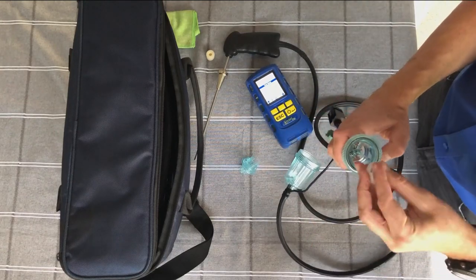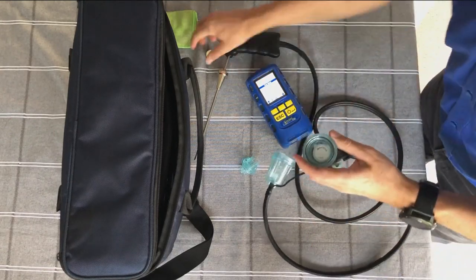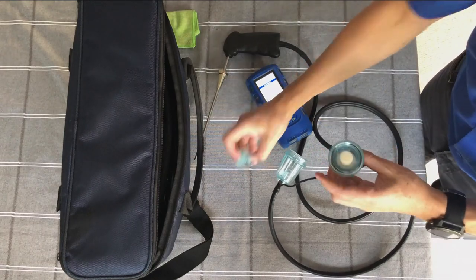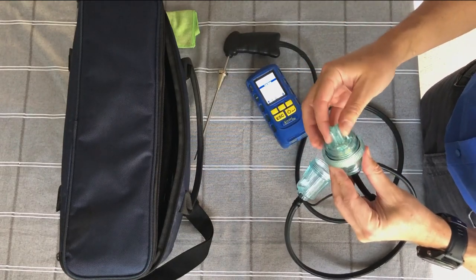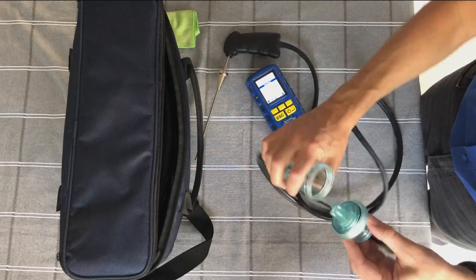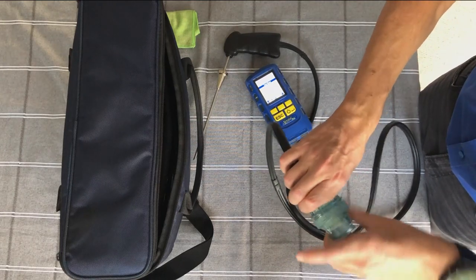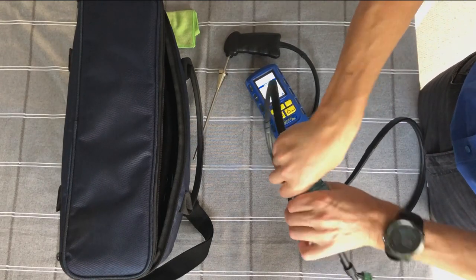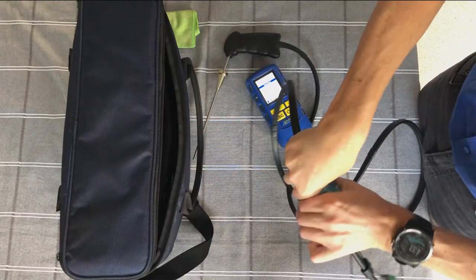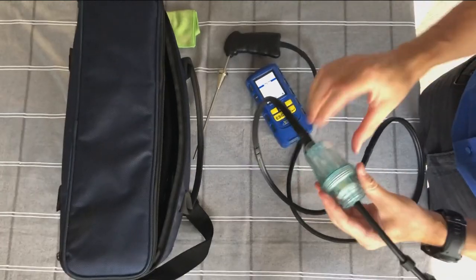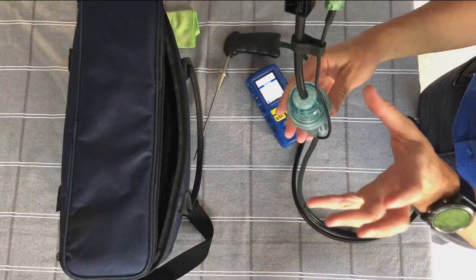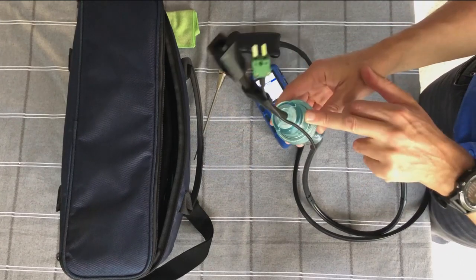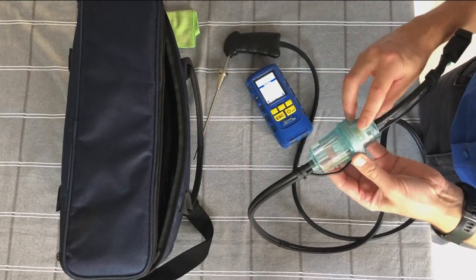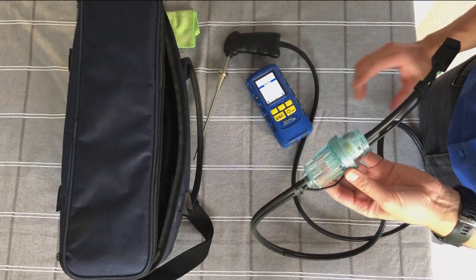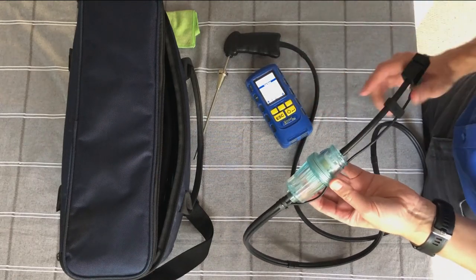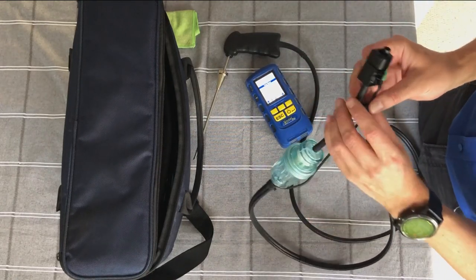Putting all that back together, once you've dried it all out, just push that in there, the filter sits on top, and then if you can see, that carrier sits in the middle and it all goes back together and that bayonet screws tight again all the way down, so you've got a nice airtight water trap. So the filtration is really, really good on Pro, and it's something we're really proud of, and it's really stopping us from getting a lot of problems with people getting water into their instrument and causing them problems.